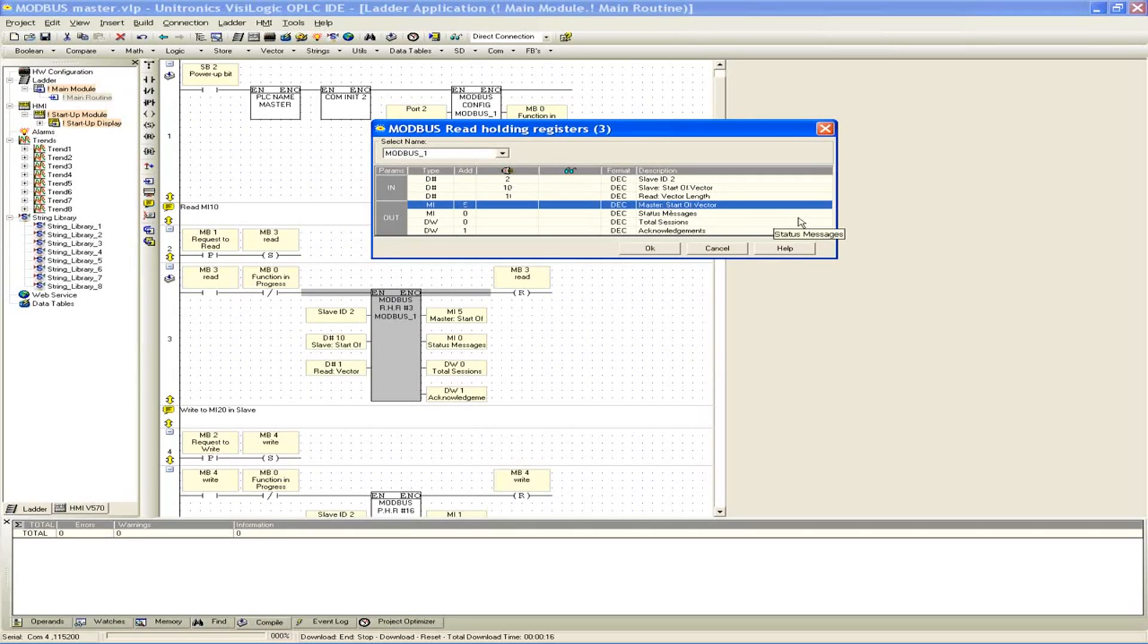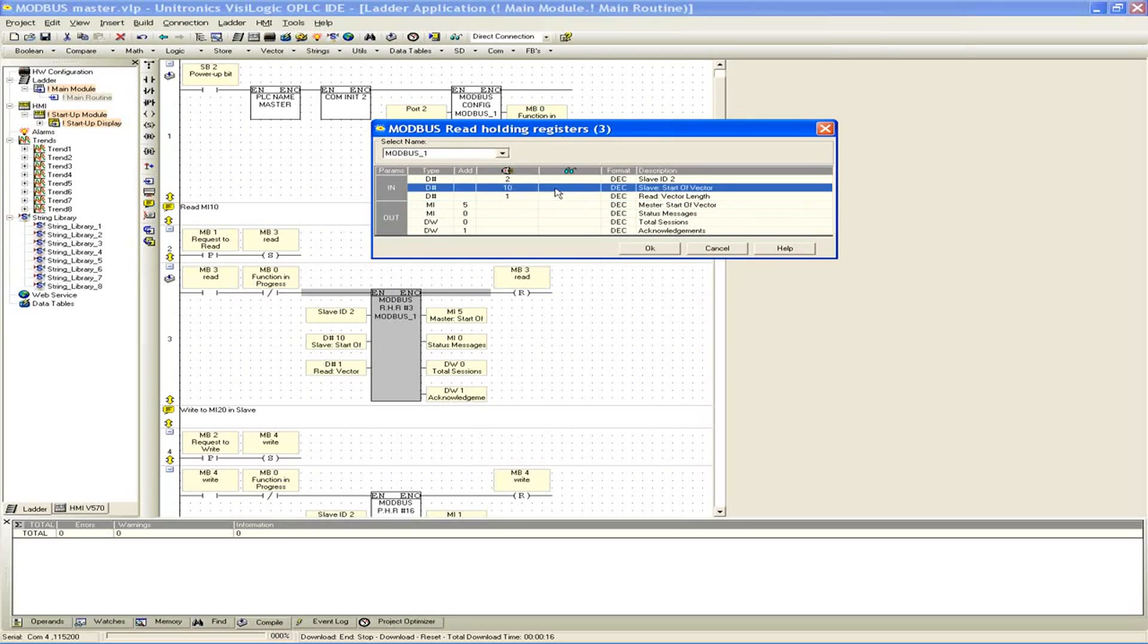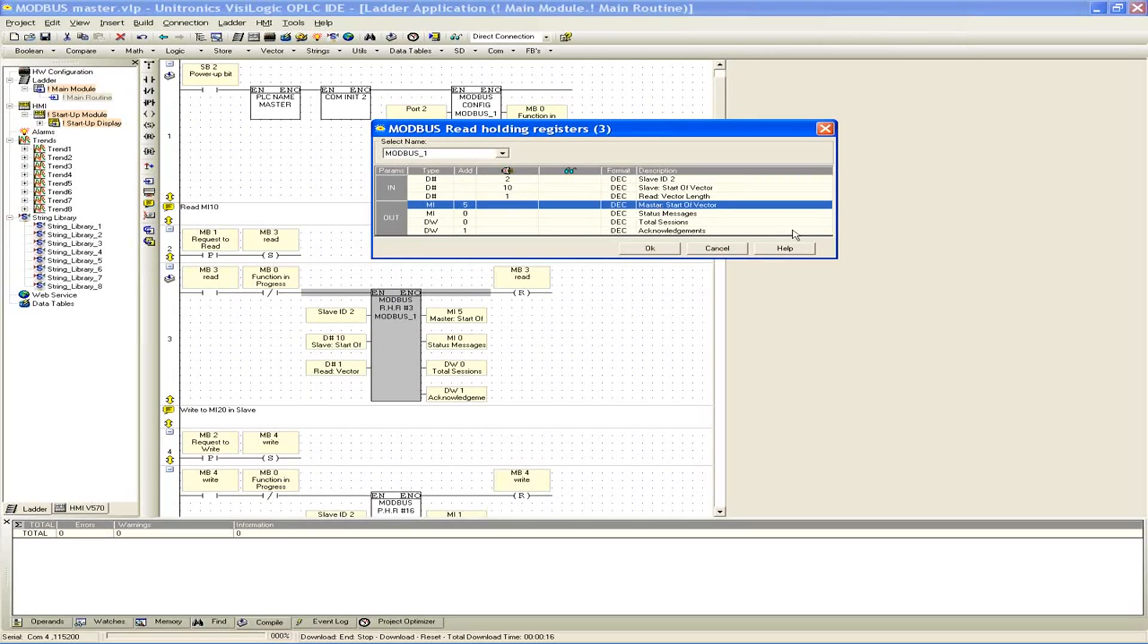Master start of vector. Now this location is where we're actually going to be placing the value that we went out and read, and it's saying we're going to store it now in MI5. So we went out and we read our address location 10, MI10, and we're going to be placing that value that we read into our master slave start of vector MI5. So MI5 is where the value that we just read is stored locally on the master device.